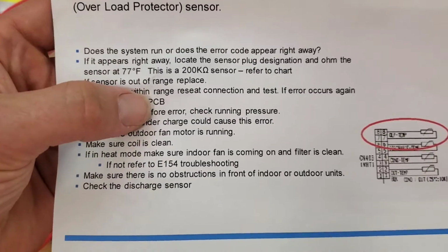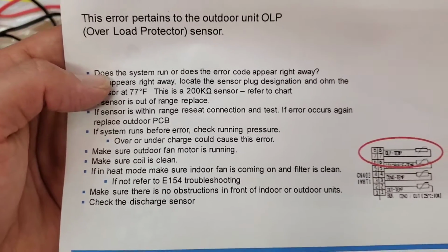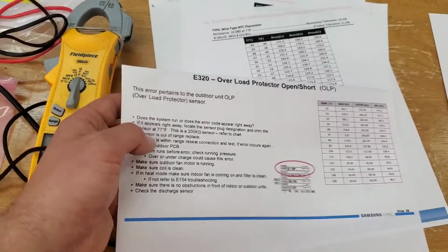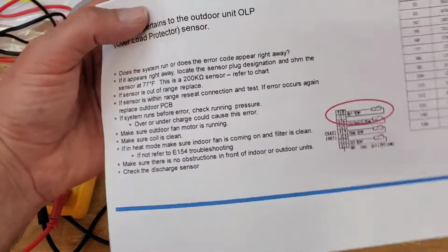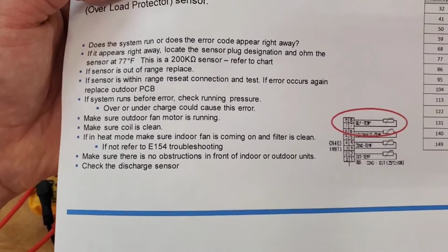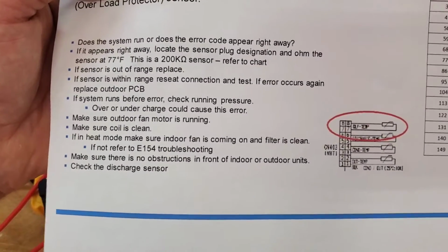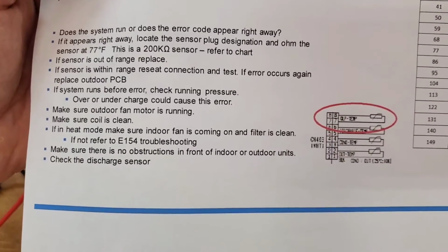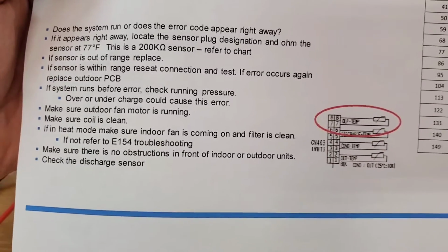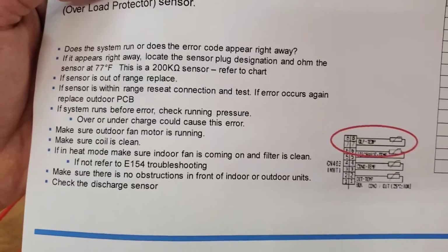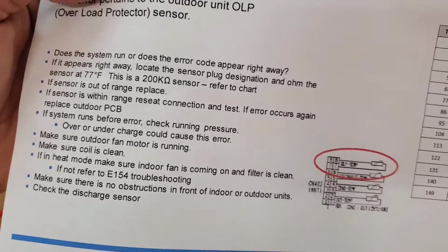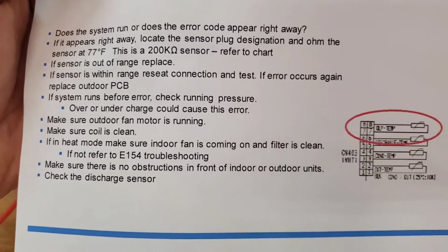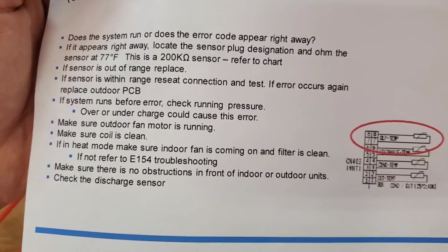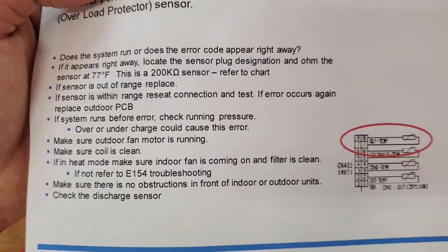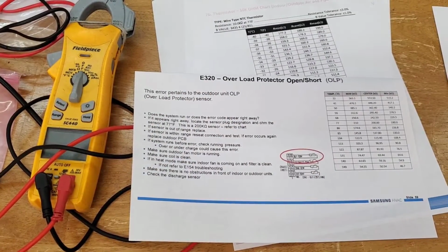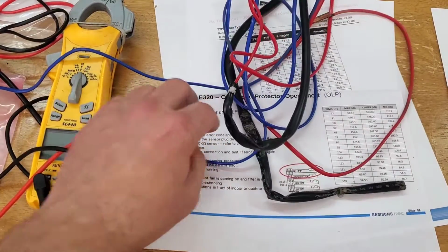So let's read on. If the system runs before the error, check running pressure. That's definitely what you need to do, because it could be that your pressures are not right. If they're not, you need to factory charge it, so definitely recover the refrigerant and factory charge. Now, make sure the outdoor fan motor is running, because that's going to affect pressure. Make sure the coil is clean. Again, you're going to affect pressure. If in heat mode, make sure the indoor fan is coming on and the filter is clean. If the indoor fan is not coming on, you're going to have definitely more head pressure for the indoor unit. You're not going to be lowering that temperature and releasing the fan. So if not, refer to E154 troubleshooting. Make sure there are no obstructions in front of the indoor or outdoor units. Check the discharge sensor. That is what you need to know. That's the first thing I want to show you. Now let's go ahead and get the OLP sensor in front of us and let's ohm it out.